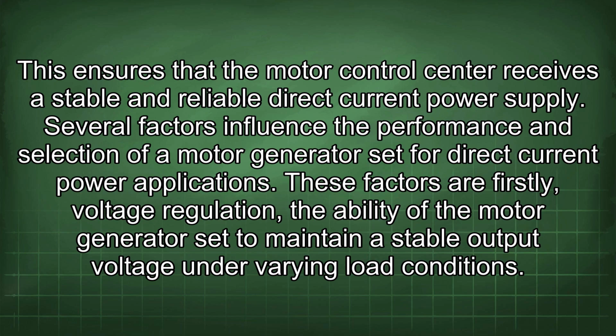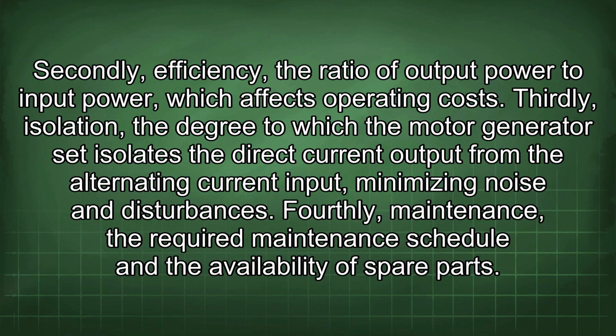Several factors influence the performance and selection of a motor generator set for direct current power applications. These factors are firstly voltage regulation, the ability of the motor generator set to maintain a stable output voltage under varying load conditions. Secondly, efficiency, the ratio of output power to input power, which affects operating costs. Thirdly, isolation, the degree to which the motor generator set isolates the direct current output from the alternating current input, minimizing noise and disturbances. Fourthly, maintenance, the required maintenance schedule and the availability of spare parts.